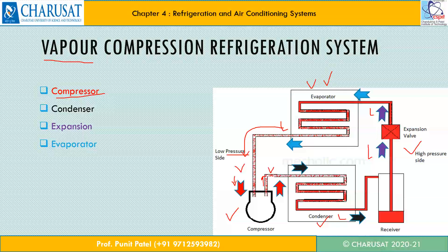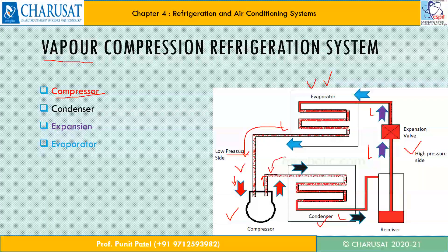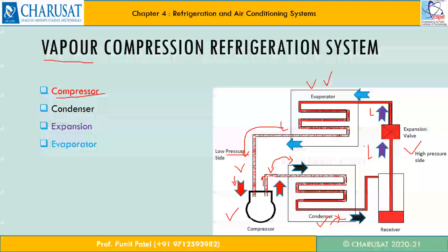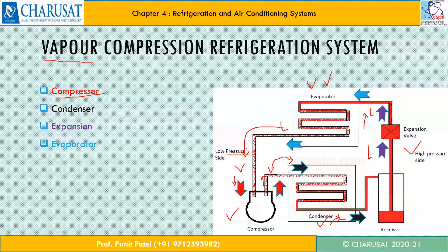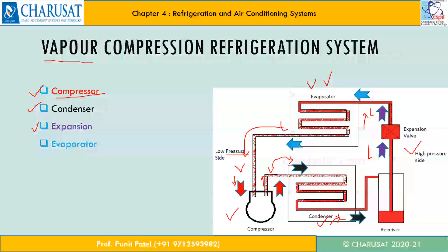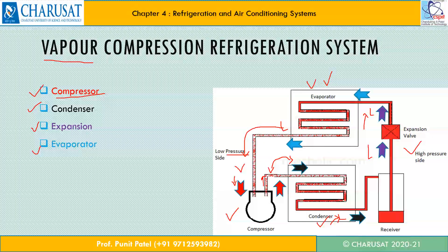That low temperature, low pressure vapor is then supplied back to the compressor, where it is converted into high pressure, high temperature vapor. Then the vapor is converted into saturated liquid in the condenser. Then the saturated liquid is converted into low pressure saturated liquid through the expansion device. And then it is converted back into low pressure, low temperature vapor in the evaporator. So it is just converting phases from liquid to vapor and vapor to liquid — the vapor enters into the compressor and the cycle is repeated. The function of the compressor is to compress the refrigerant and convert it into high pressure vapor.